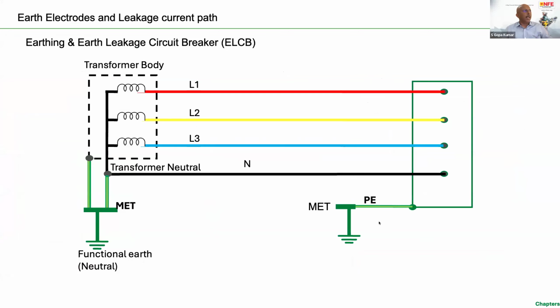Let me explain how to read this particular circuit. You can see that there is a source on the left side: a transformer with three-phase windings, and the neutral is earthed. Then the phase and the neutral come to the equipment, probably through a main distribution board and a sub-distribution board, to a final equipment. Now the equipment body is connected to a PE conductor and finally to an earth electrode. This is a typical, small example of an electrical installation.